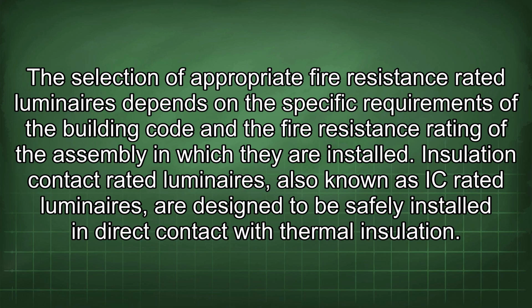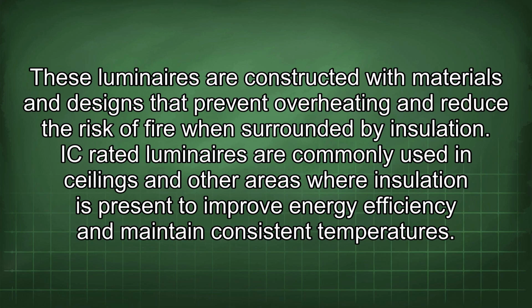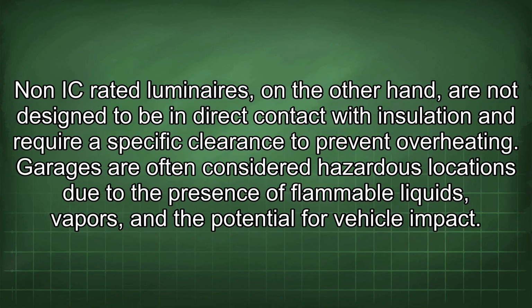Insulation contact rated luminaires, also known as IC rated luminaires, are designed to be safely installed in direct contact with thermal insulation. These luminaires are constructed with materials and designs that prevent overheating and reduce the risk of fire when surrounded by insulation. IC-rated luminaires are commonly used in ceilings and other areas where insulation is present to improve energy efficiency and maintain consistent temperatures. Non-IC-rated luminaires, on the other hand, are not designed to be in direct contact with insulation and require a specific clearance to prevent overheating.